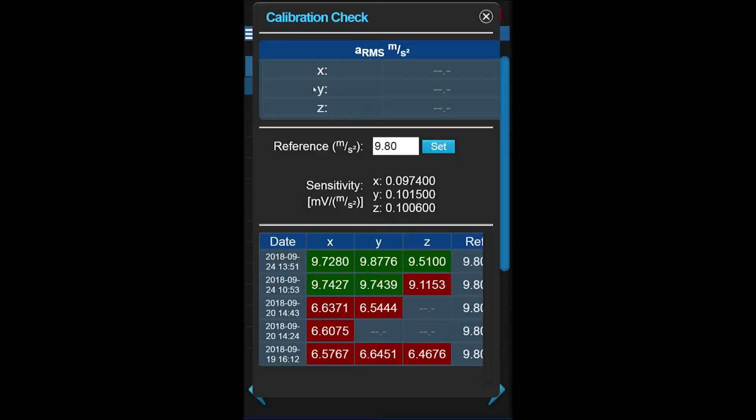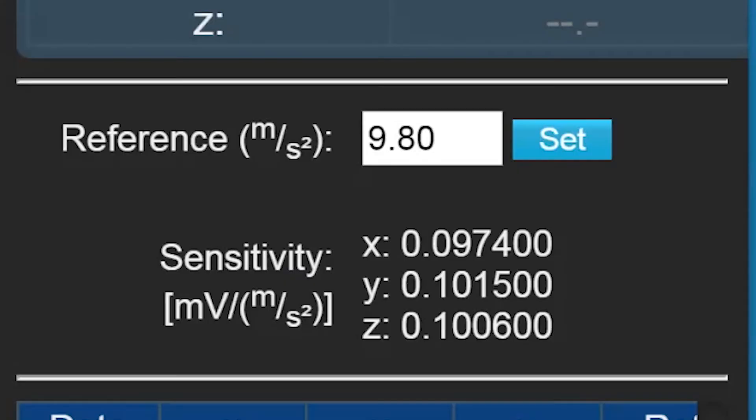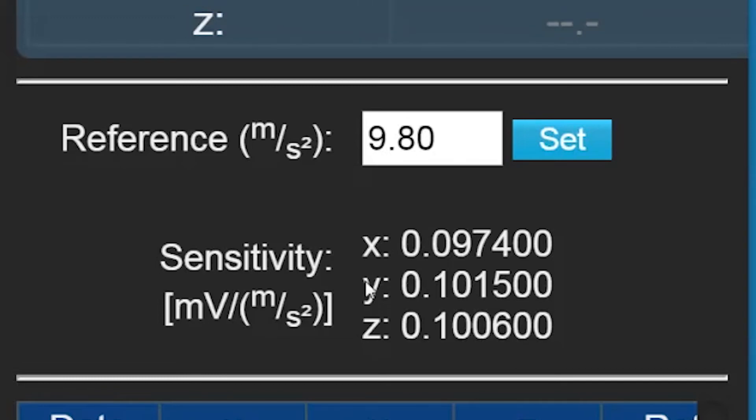Enter the reference value for the shaker you will use to perform the calibration check and click Set. This value is usually provided with the shaker reference documentation or on the shaker itself.